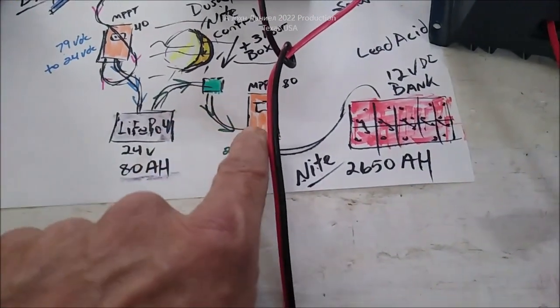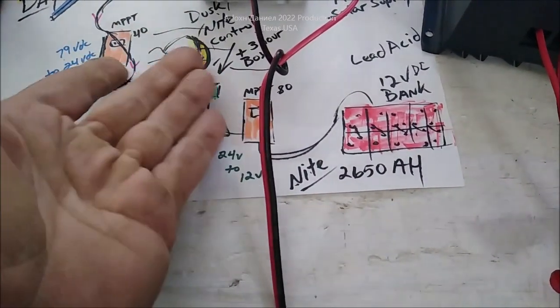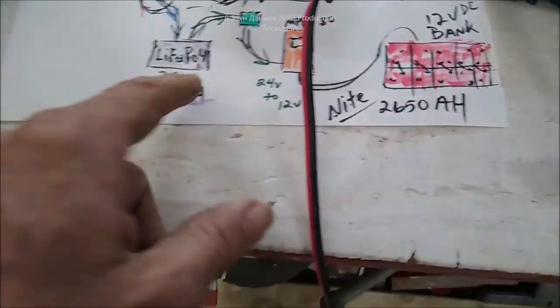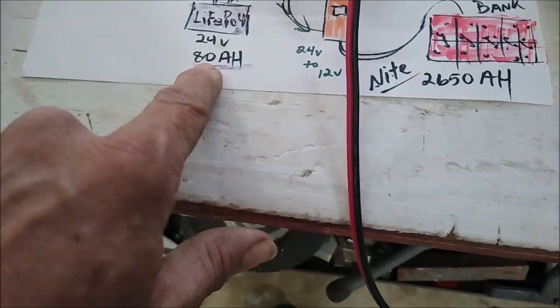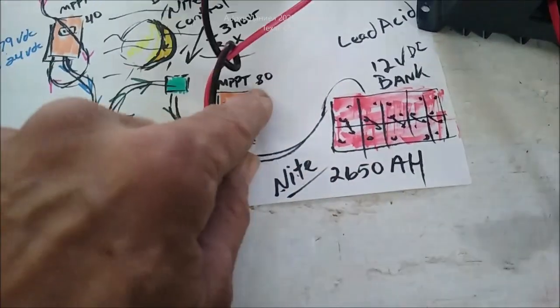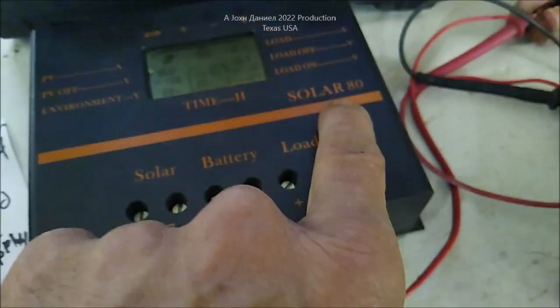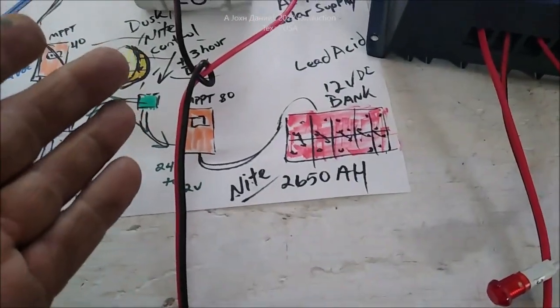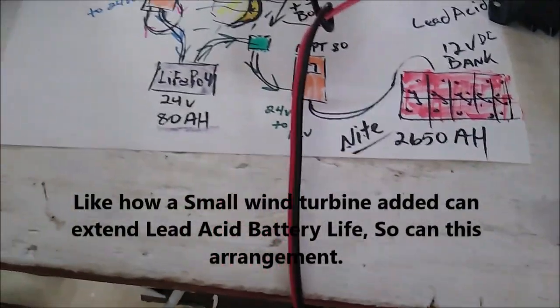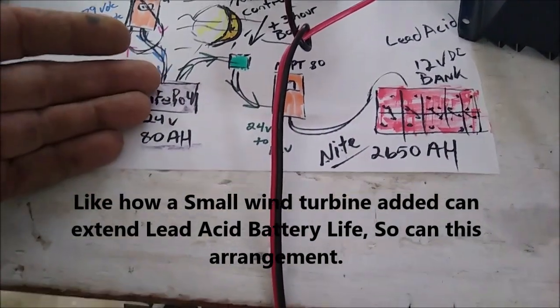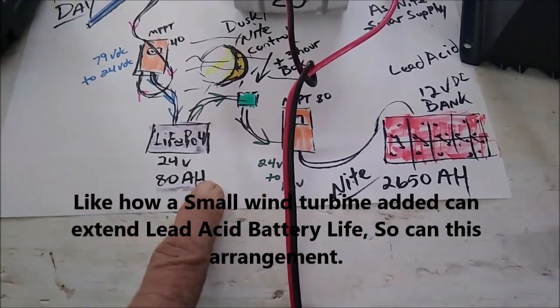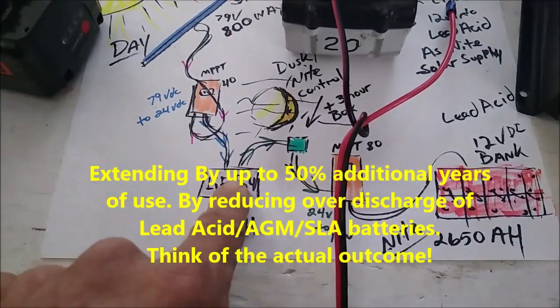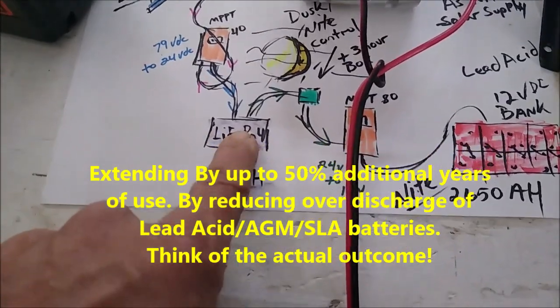So that's going to send power now, just like the sun came up and the solar panel came on. Now your maximum potential and your maximum potential, see, 80, 80, you want to stay within those bounds. Now these can pull more, but if you stay within these bounds, you can run this down to 0% basically. This will take it back and start charging it again because the BMS will cut this thing off at 5%, and it'll still show a registered voltage to keep that alive.